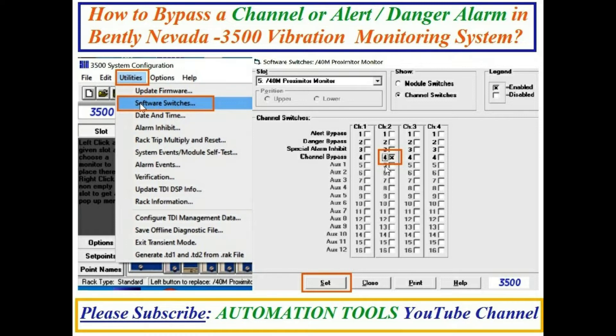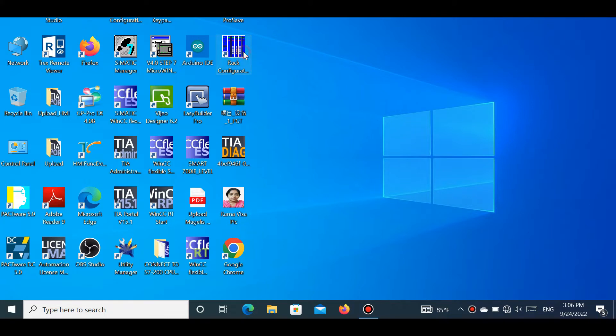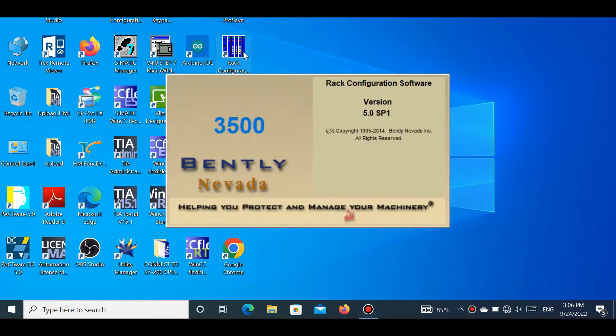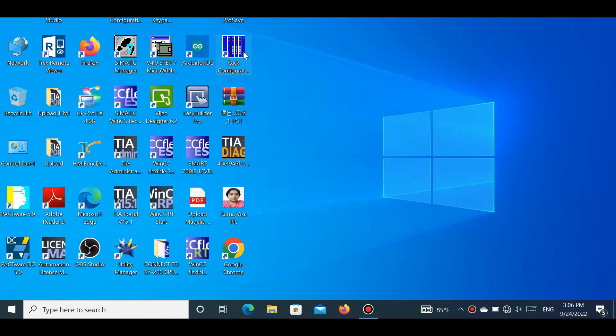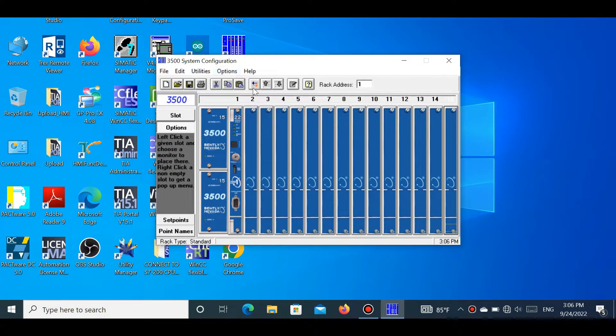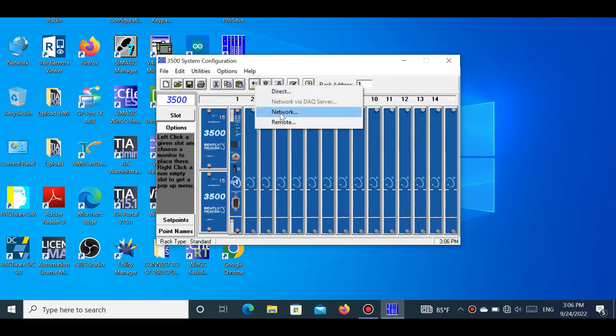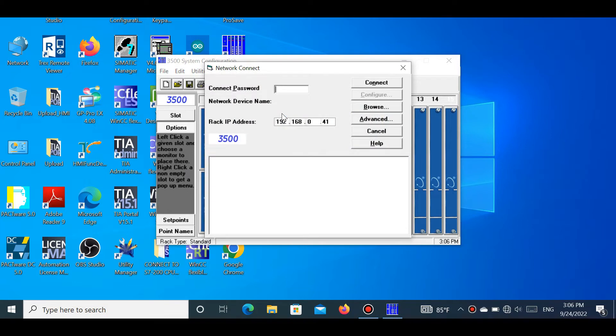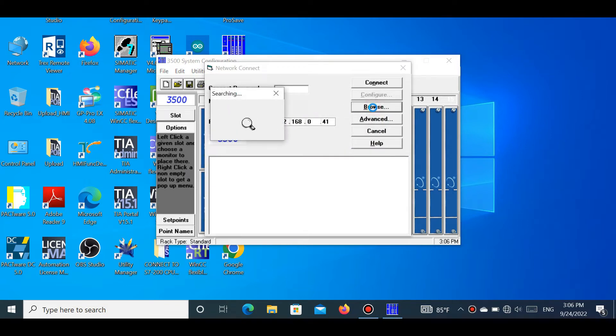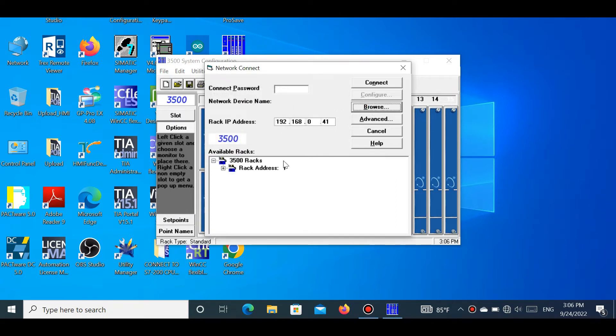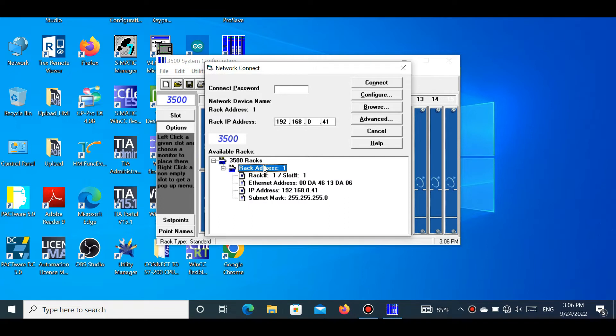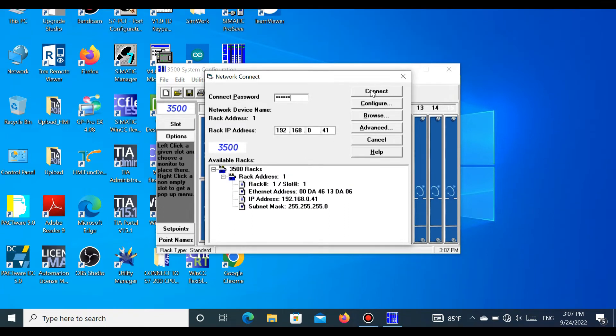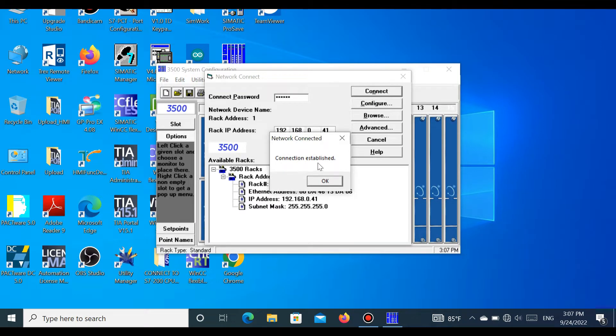Let's get started. First, open the Bently Nevada configuration software 3500, then go to the connection button. If we want to bypass a channel or alert, we first have to upload a program. Press Connect, then the Browse button, and find the rack that is connected with the laptop or PC. Select the rack and press the Connect button. Connection is now established.